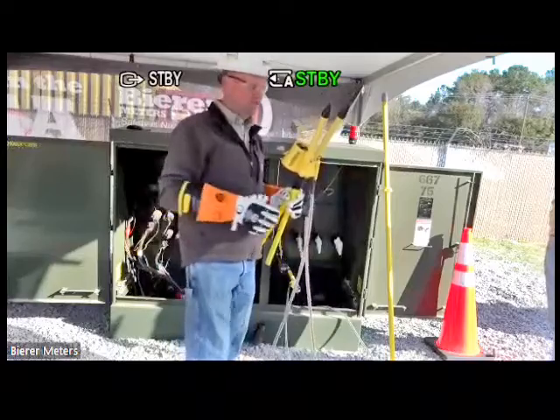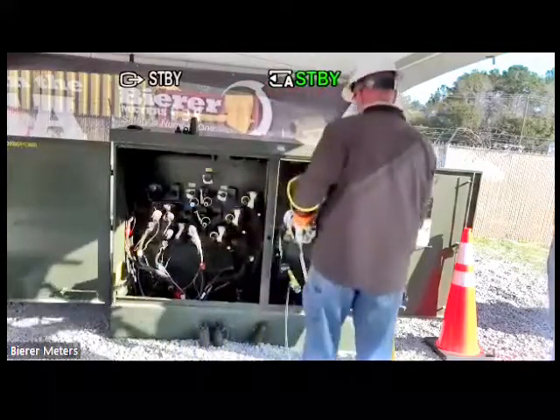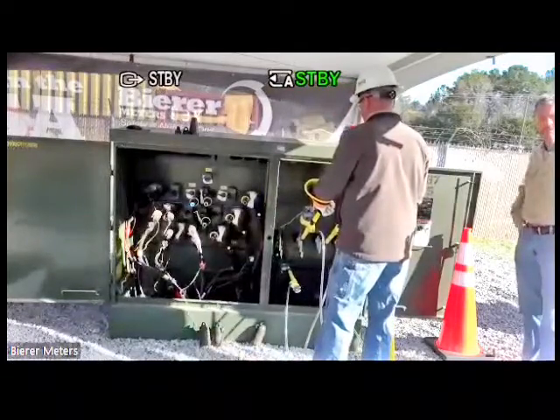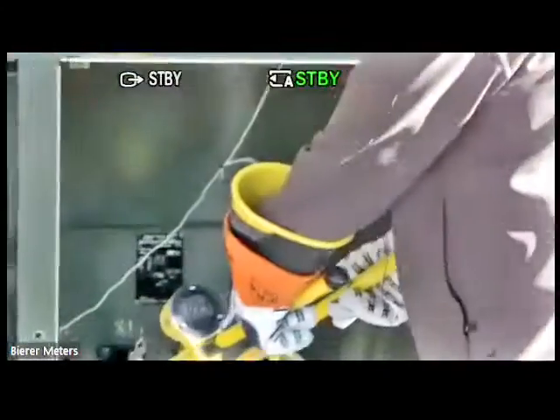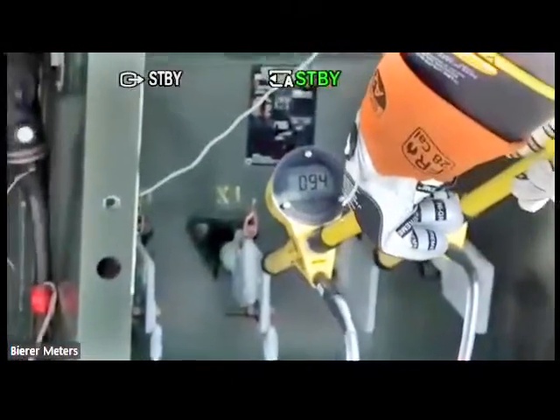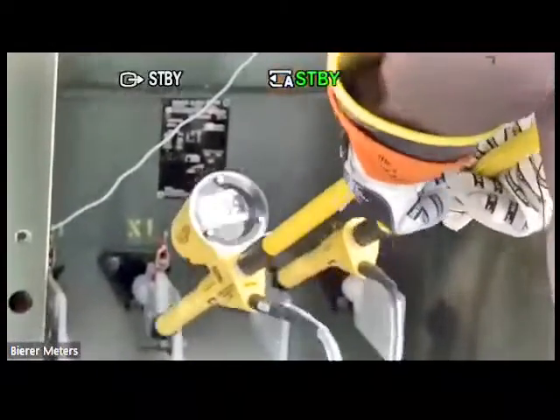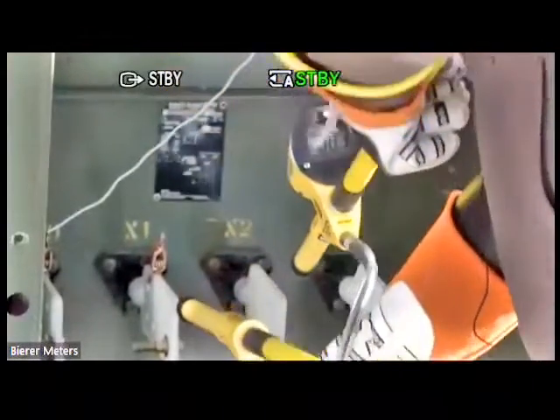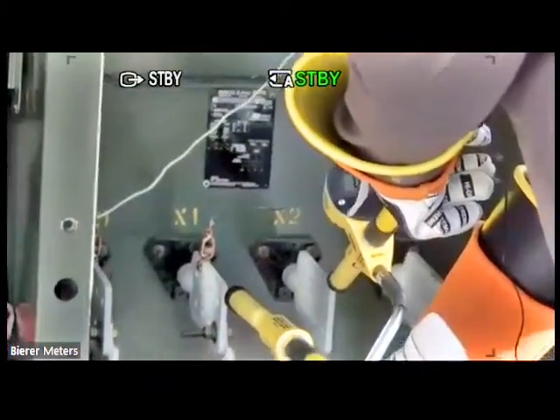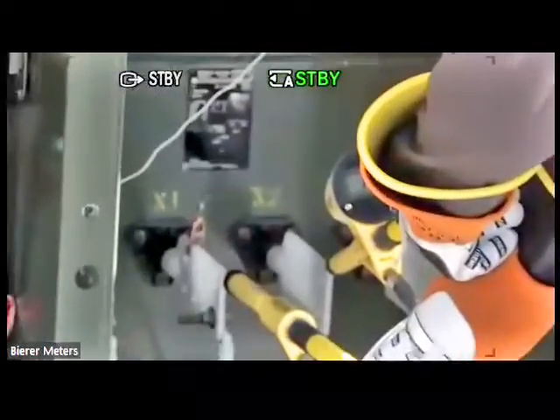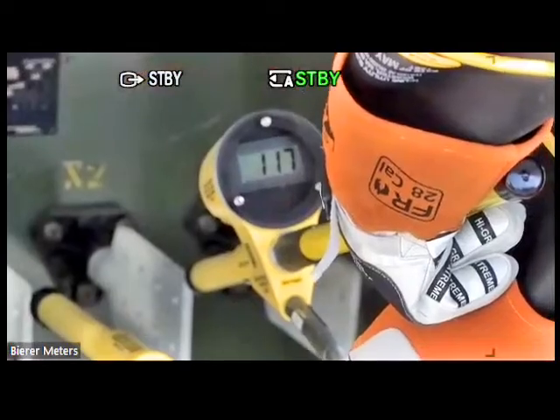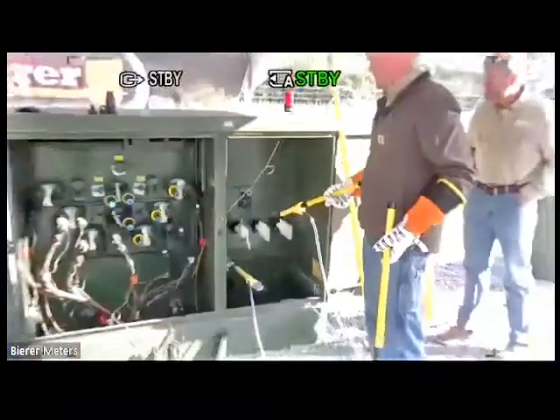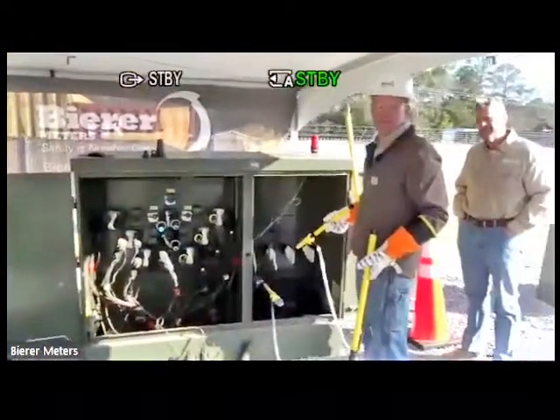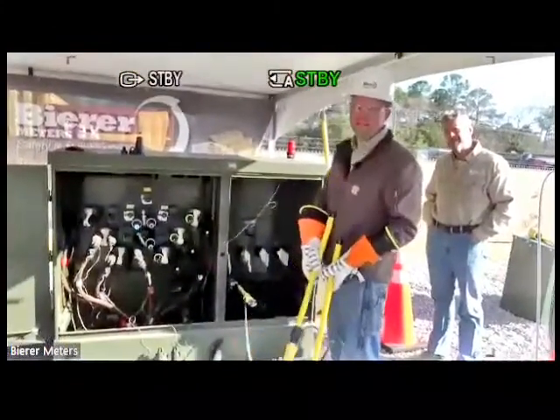So again, additional safety built into this. But I'm going to take my reading. I'm going to pick the left one and the center one, and I'm going to take my reading here and see what I get. So I get a 95. I'm going to get Ryan to move the camera. Okay. I'm going to swap the two and take a reading again. And I get a 116. You see that, Ryan? Okay. All right. So this X2 bushing had a higher reading than the X1 bushing. So that phase is leading.